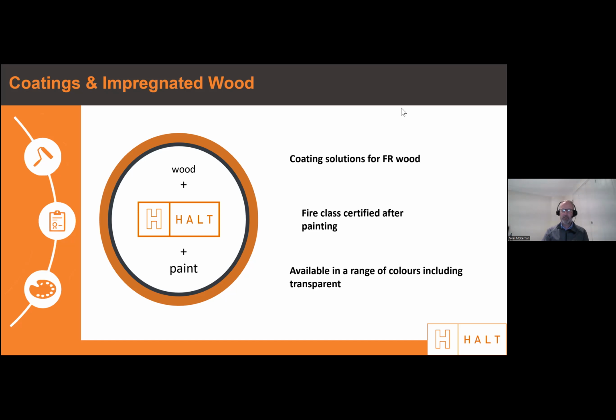We go back through the same process: we classify the raw material, then coat it using a certified process where we can closely control the amount of coating applied. This isn't an intumescent coating, just a cosmetic one, but you have to demonstrate that the coating, even if water-based, doesn't alter the declared performance of the product as tested in its raw format. So we can achieve certification and classification for coated FR timber, but we have to redo the whole testing process - take the raw product, test it, coat it, test again - and at the end you have another CE certified option, confirming the coated timber has the same declared performance.